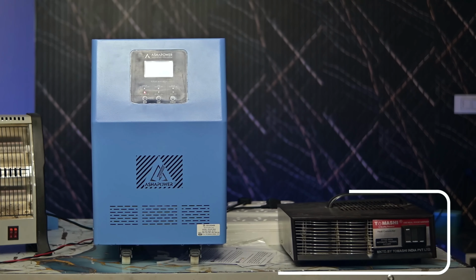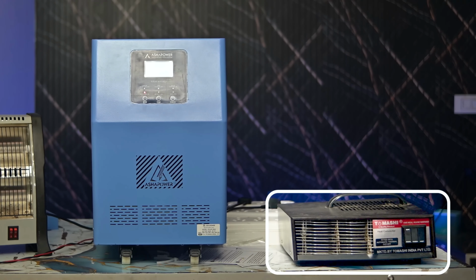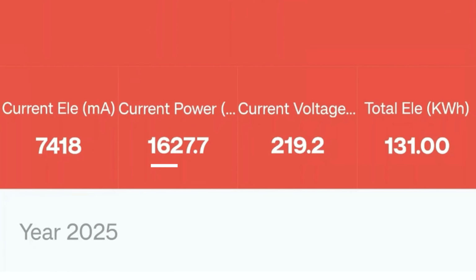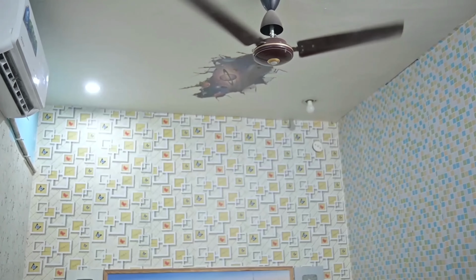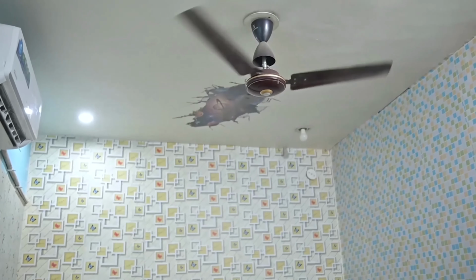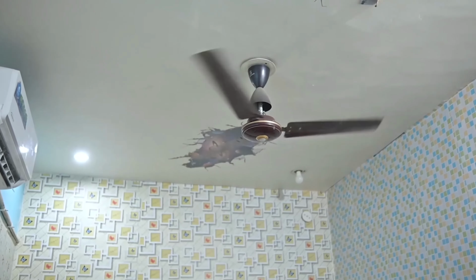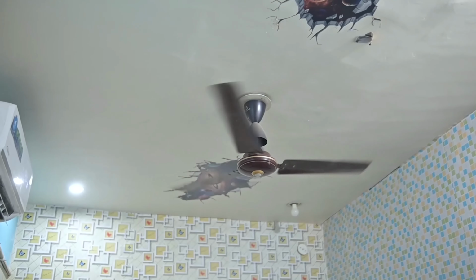First of all, calculate your total load properly, and you should not calculate load just by guessing from appliance labels. Do not simply assume that your fan is 70 watts or your room heater is 2 kilowatts. Actual power consumption is usually lower. For example, we tested a 2 kilowatt room heater and in actual use it was consuming only around 1600 watts. And if we talk about other appliances like ceiling fans, then a normal AC fan consumes 70 watts only when running at full speed. And if it is a BLDC fan, then it consumes around 30 watts only.